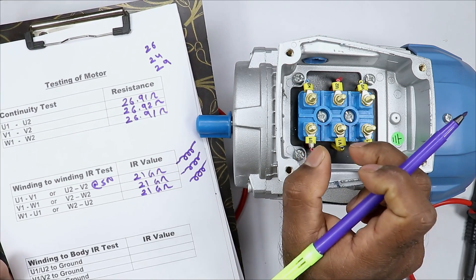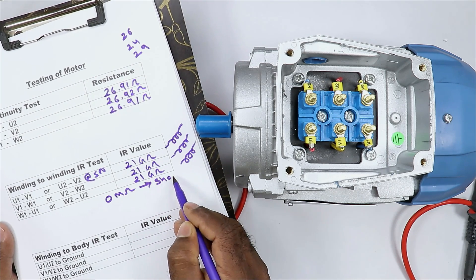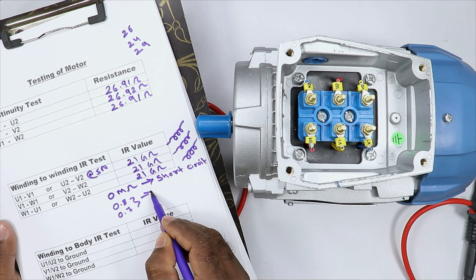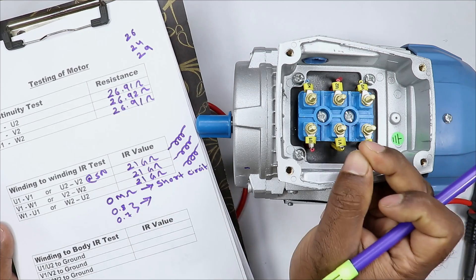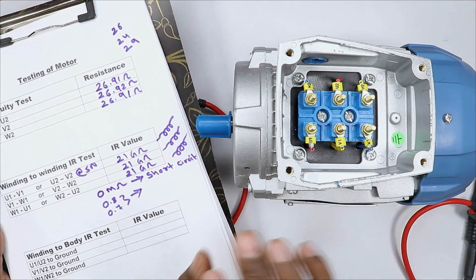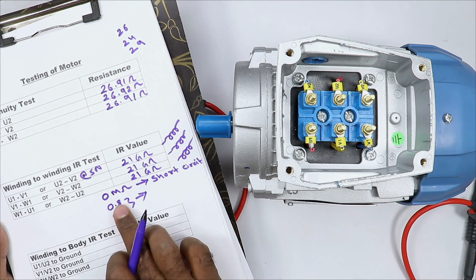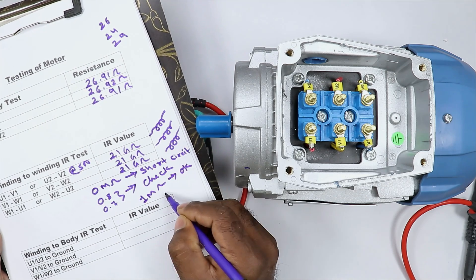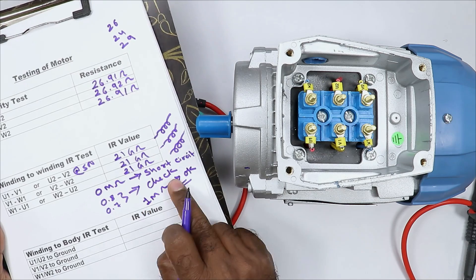If you measure IR value and you get 0 mega ohm, it means the winding of that motor got short circuited. Besides, if you get values like 0.8 or 0.7 mega ohm, then the insulation of the winding got weak and those windings are soon going to short circuit with each other. It means if you get less than 1 mega ohm, the motor needs to be checked. Causes can include dust or water inside the motor, which also decreases IR value. If IR value is more than 1 mega ohm, then the motor is fine. IR value of the motor must be at least 1 mega ohm.